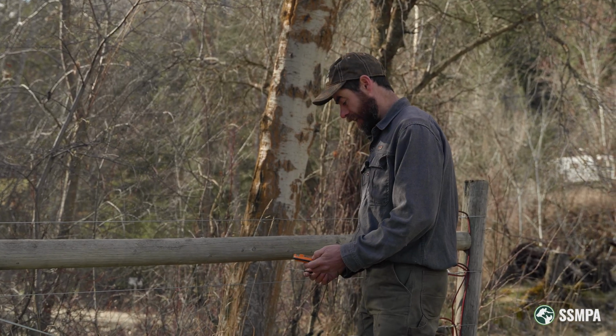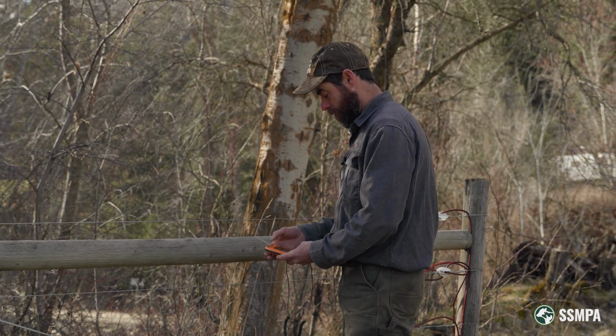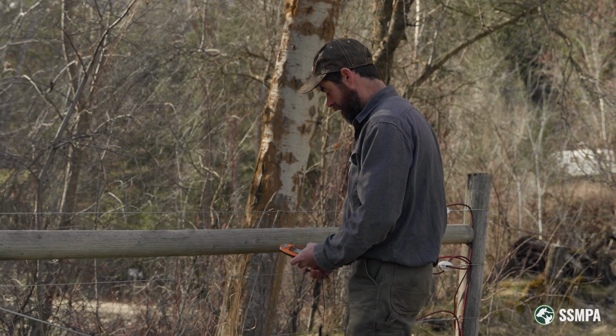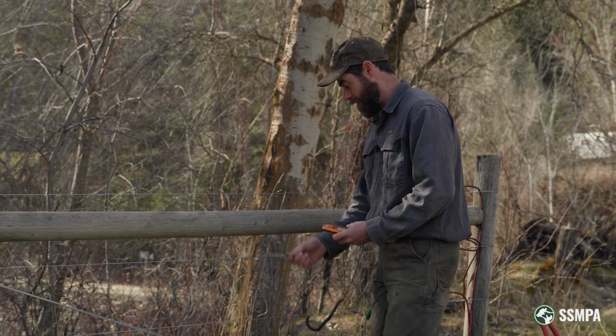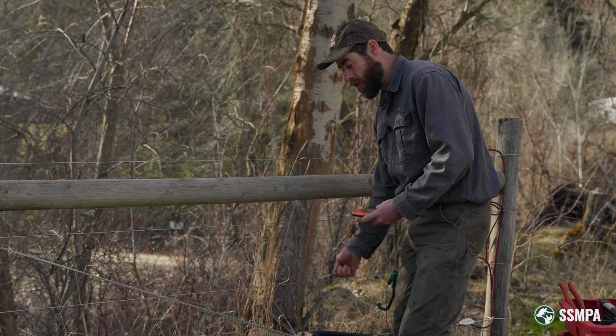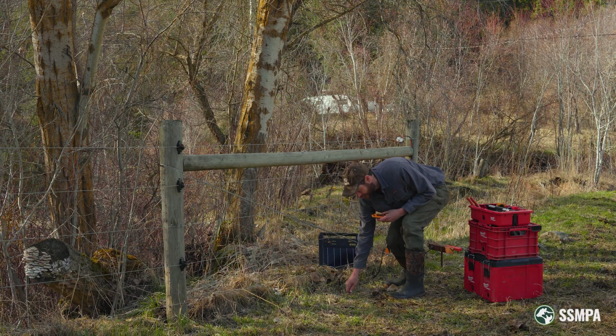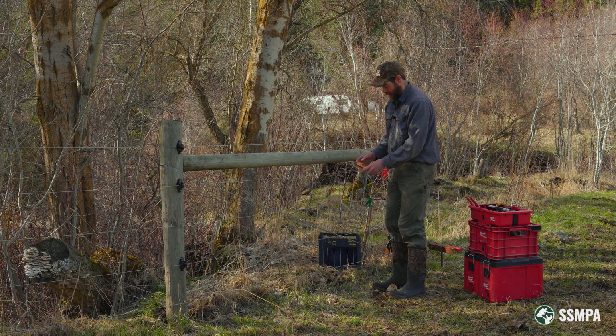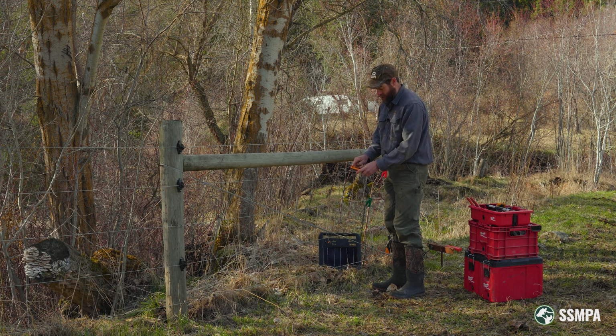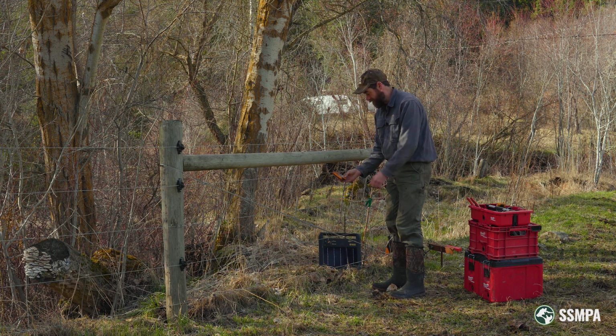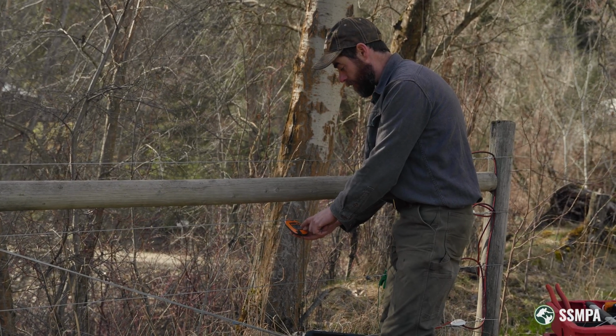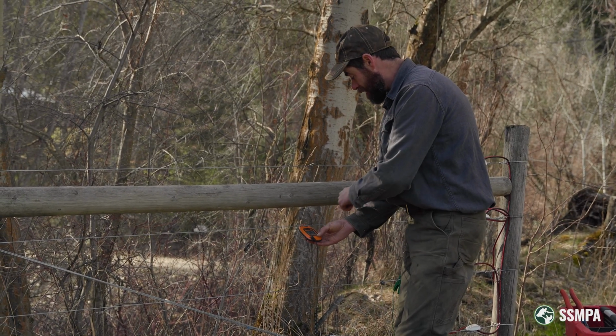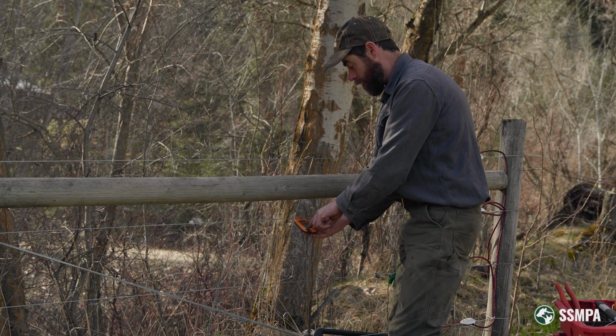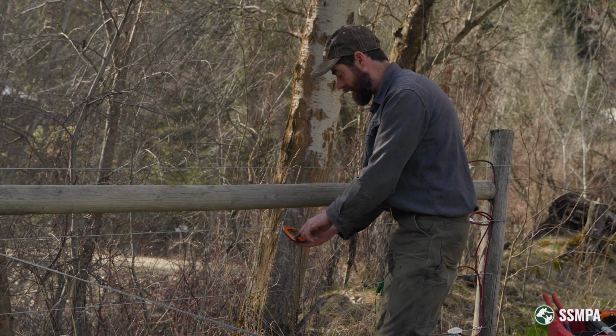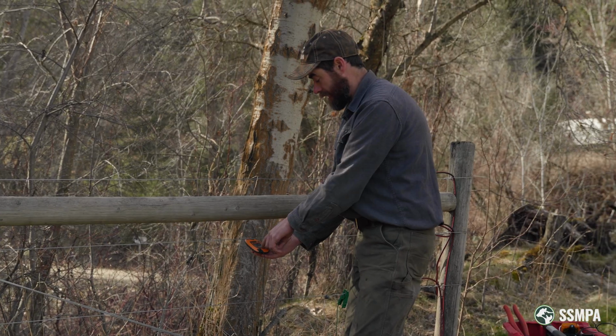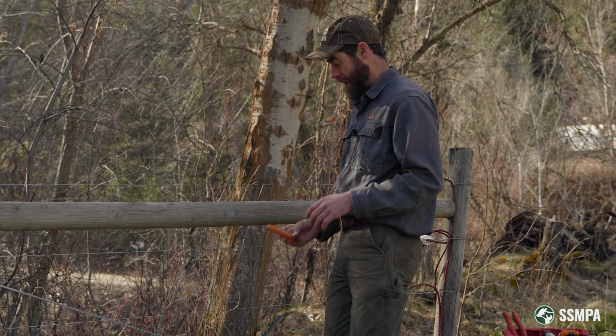So how we're going to check that is using your voltmeter, or ideally your fault finder. We're going to touch the ground probe here to the ground wire on the fence, or put it directly into the earth to get your measurement. And then we're going to touch the steel portion right here to the hot wire of the fence. And while we're holding it like that, we're going to get our reading. In this case, the fence voltage on this system that's performing well and has no major faults is 6.8 kilovolts. That's 6,800 volts. So that's going to be our baseline.